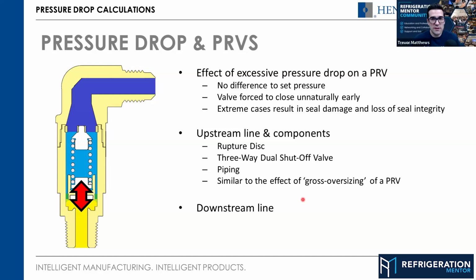Yeah, because what we want to do with the pressure relief is let out enough so that when it seats again, it's at a safe pressure in the vessel, or whatever you relieve from, to hopefully not relieve again. Is that correct? Correct. Yeah, the valve needs to open and discharge. I would call it discharge naturally, a nice smooth hiss of noise as it's designed. If you restrict it in either of these ways, then you're forcing it to close, but it's not ready to close yet, so it wants to open again. And this is where you get the chatter.